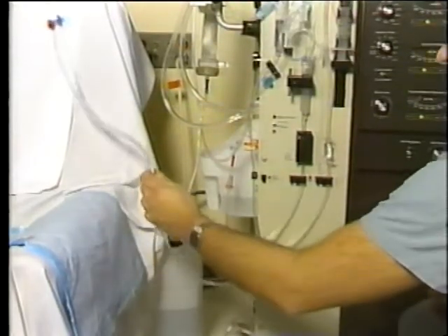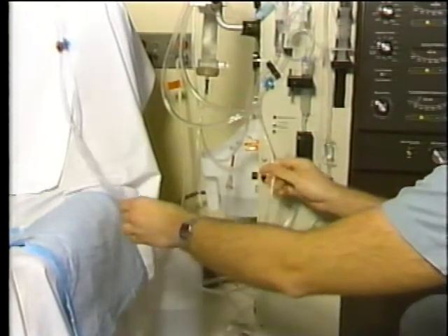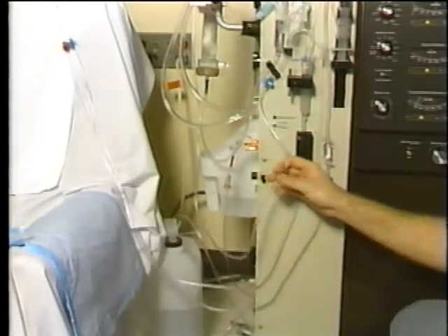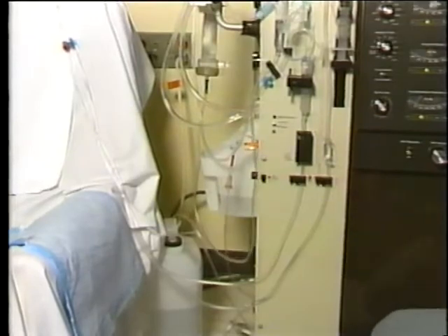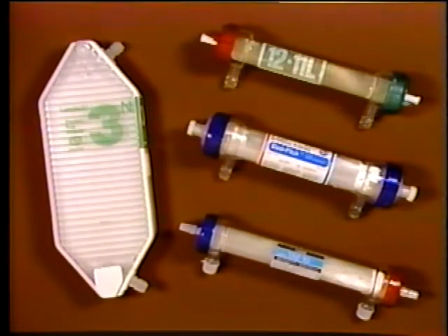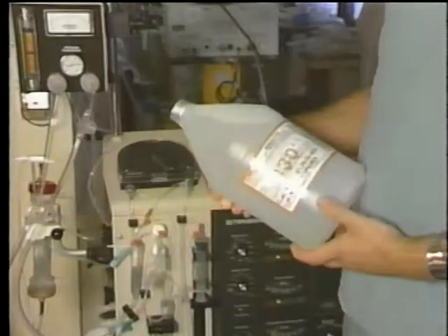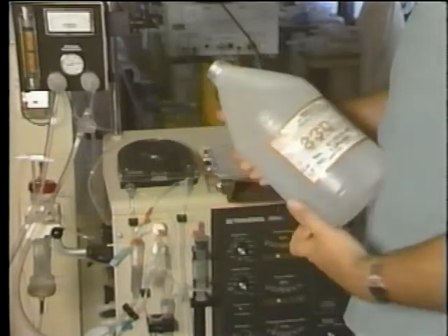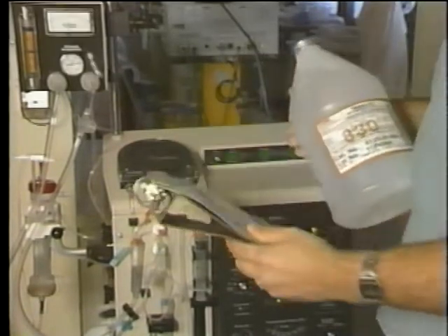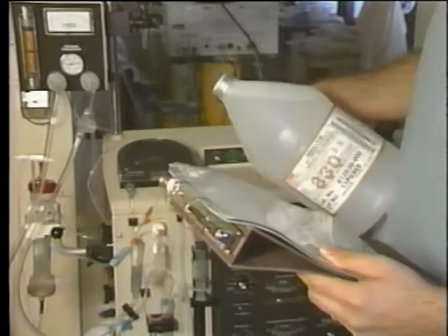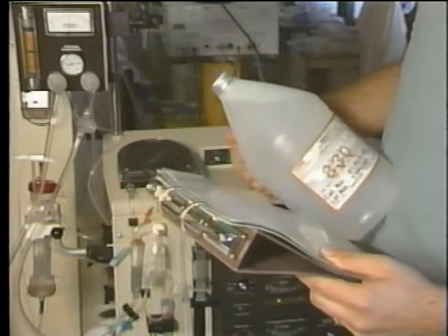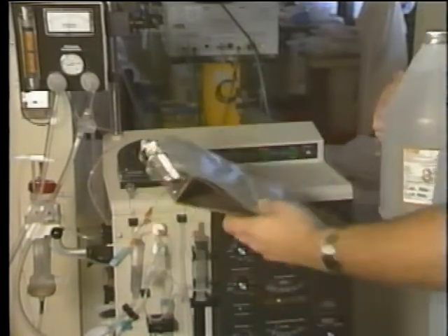Visual inspection of the blood circuit assures sterility and integrity of the lines. Air should not be present. Check the dialyzer and the patient's chart to verify that it is the correct dialyzer for the patient. Again, check the patient's chart to assure that the concentrate formula is that prescribed for the patient and that there is enough concentrate to complete the entire treatment.